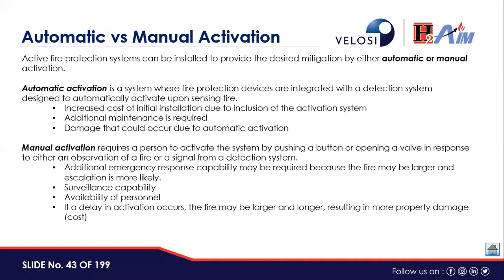For example, if you have a fire and gas detection system, based on the fire zones and the number of detectors in each fire zone, confirmation of the event, an automated spray of water or foam can be started, or the system might be activated based on automated signals, or it could be manual startup or manual activation, or it could be a semi-automated system as well.